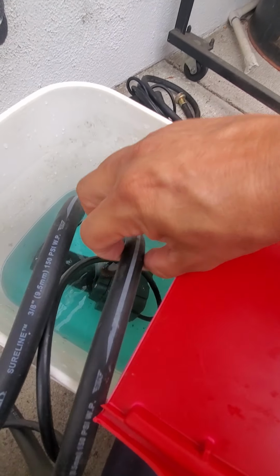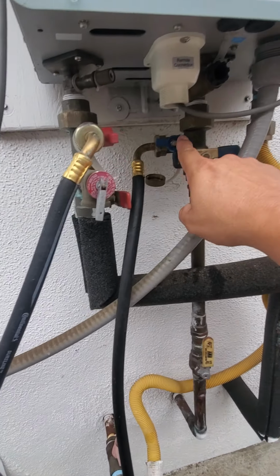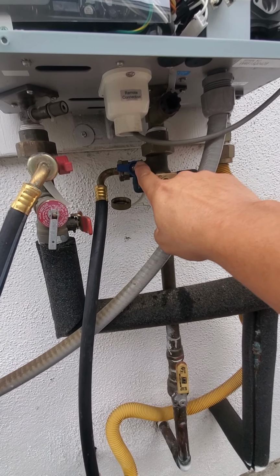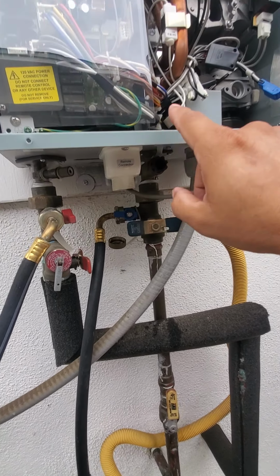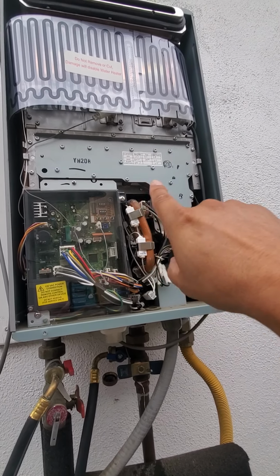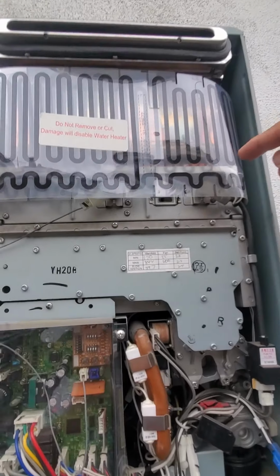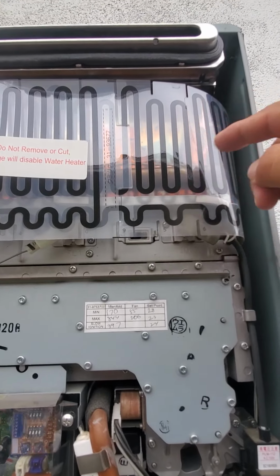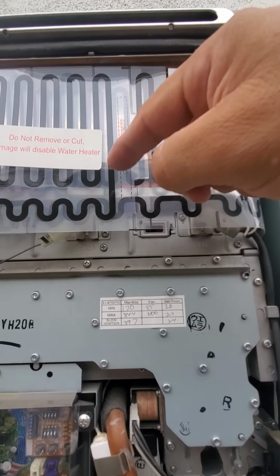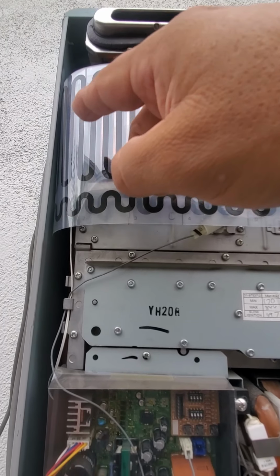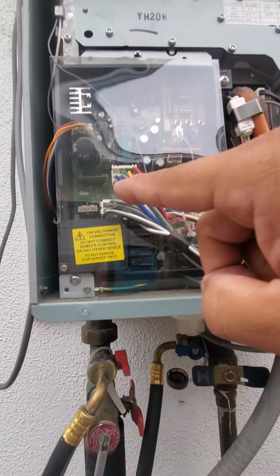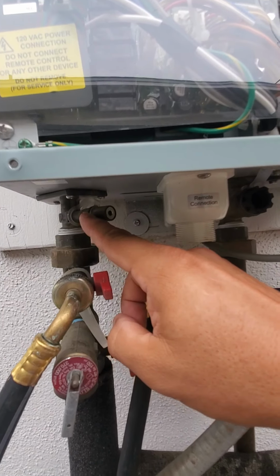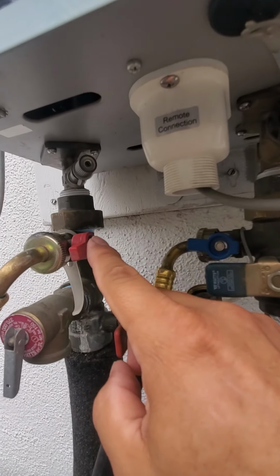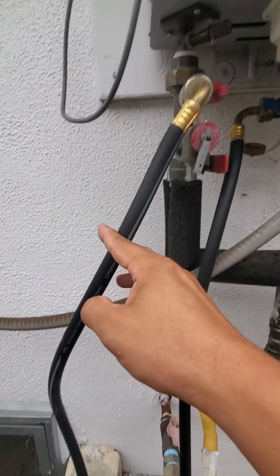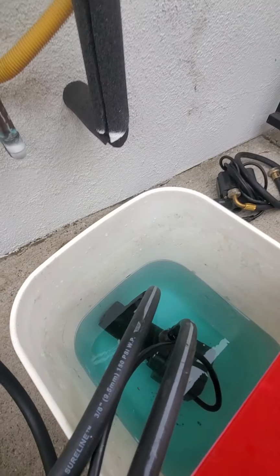Basically this pump pulls that water, runs it into here and into our cold, and it goes into the heater, which eventually all that descale goes through the heat exchangers — this actually has a graph of how the heat exchanger works — and all those coils get cleaned up, absolutely clean, comes back down to the hot out here through our hot service port, goes out this way and then back into our bucket.